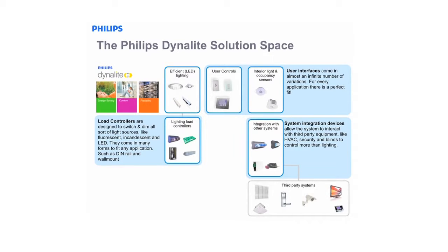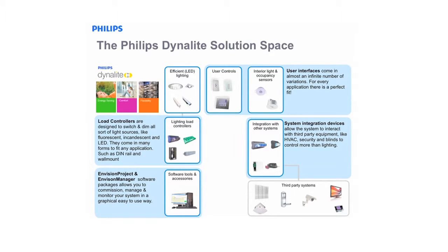Integration devices allow for third-party systems to seamlessly integrate together. This can reduce the amount of times an end user needs to interact with the different systems in an area. For example, if the air conditioning and lighting control are integrated together, then the lighting control sensor can be used for both systems, reducing the number of user interface devices required. Software allows for end users to control their personal lighting from their very own PC, and there are opportunities to use a worker's PC for occupancy detection.